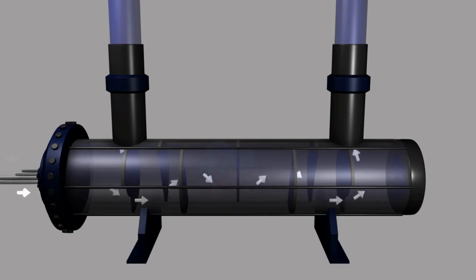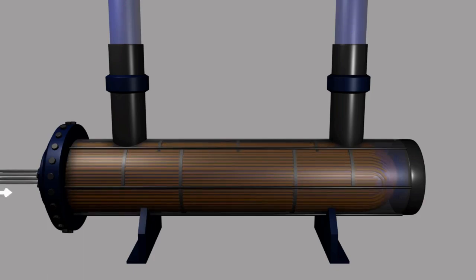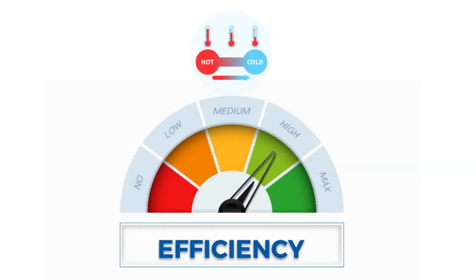The baffle plates inside the shell cause the fluid to flow in a serpentine pattern, increasing the amount of time the fluid spends in contact with the tubes and maximizing the heat transfer efficiency.